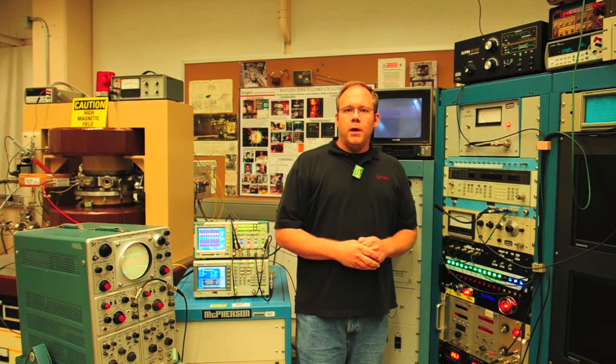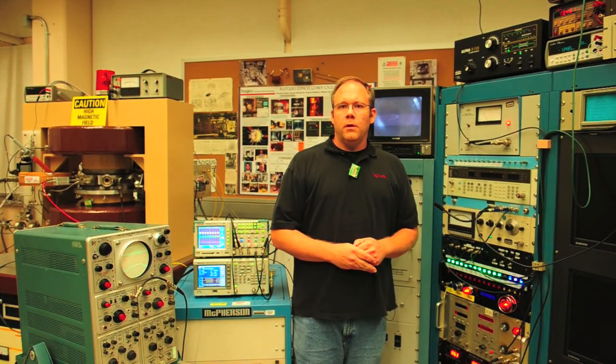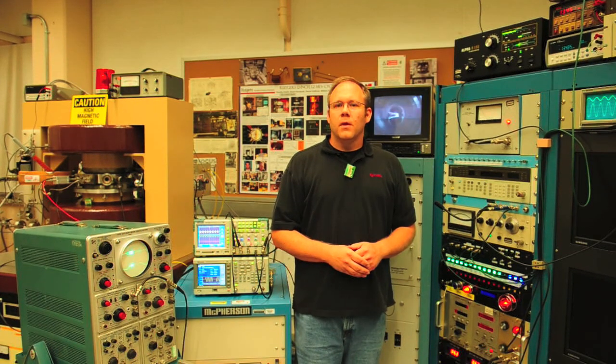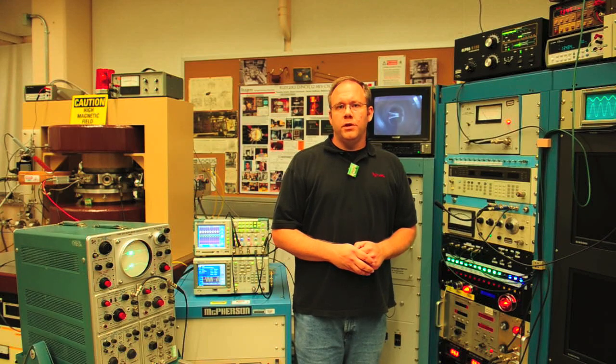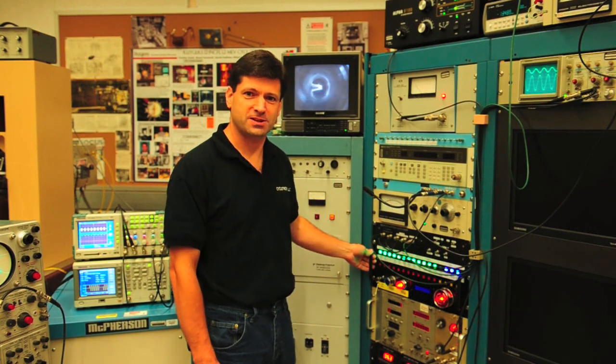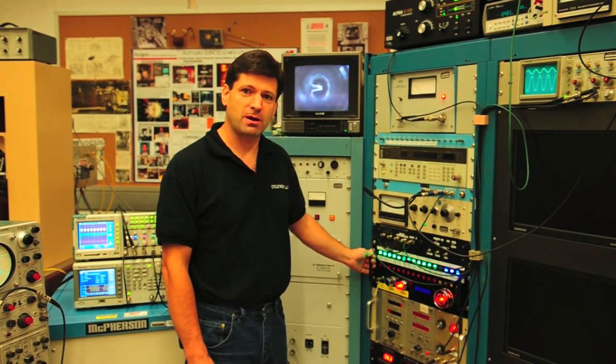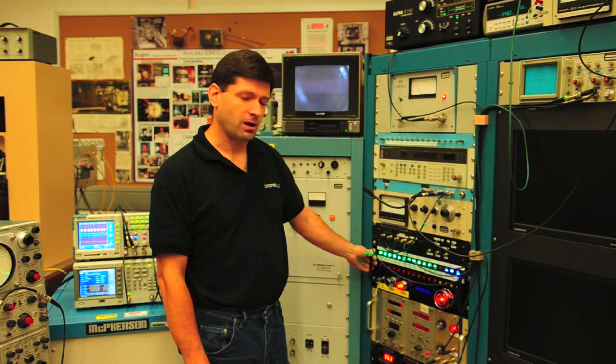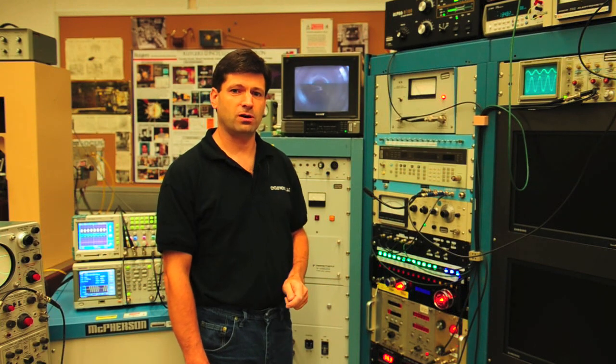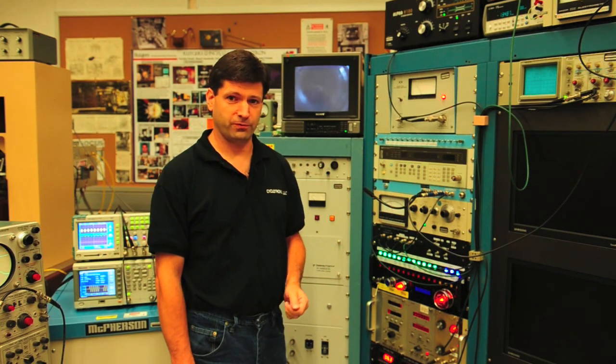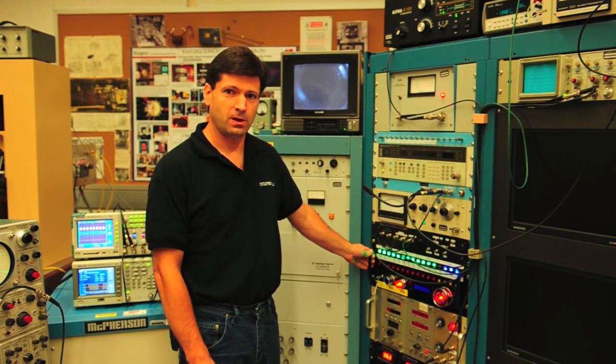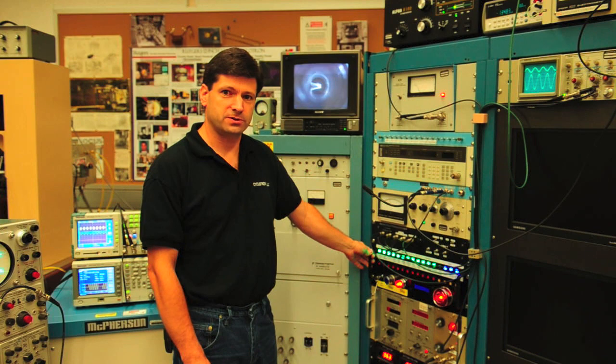We have developed a PLC, or Programmable Logic Controller based interlock system that will shut down the cyclotron quickly if an unsafe situation presents itself. The PLC based system has been devised by Jim Kutzler, who will tell us a little bit more about it now. We want to show you the machine safety system that we put together. It's based around a Programmable Logic Controller. A Programmable Logic Controller was selected and used for this because it's a very robust, simple, straightforward piece of hardware that performs a job that performs it well.